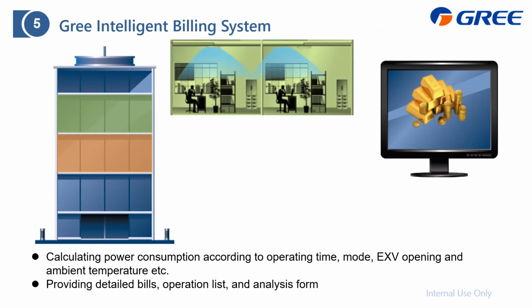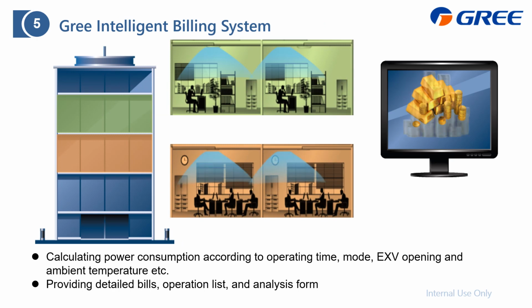Intelligent billing system. That means if some companies or some persons share the GMV system, it is okay because all the indoor units are separated. But when they need to pay the bill, the system is together. It's not that easy to separate the bill, right? And for our system, when you apply this billing system, it is very easy because we already record how the indoor unit operates, including the fan speed setting, temperature setting, and also how long it operates. That means we already know how much capacity it consumes from this indoor unit.